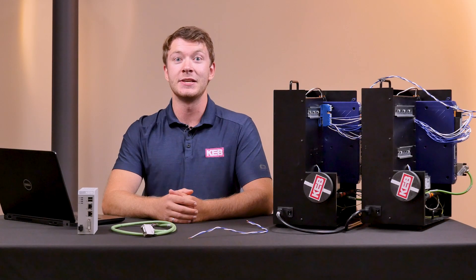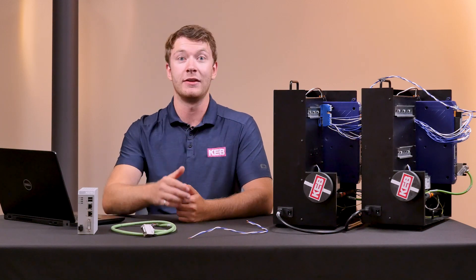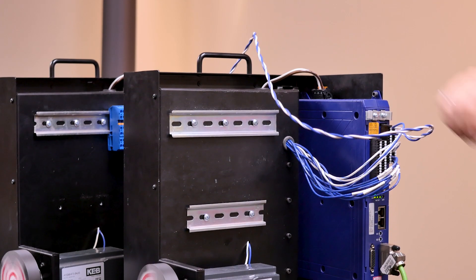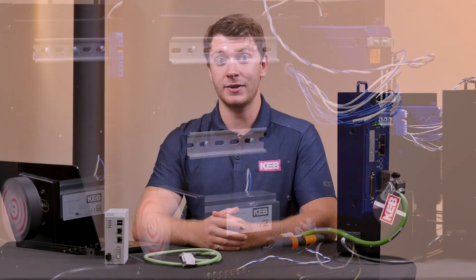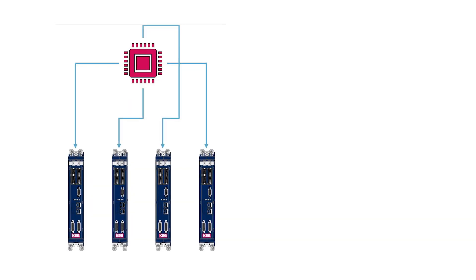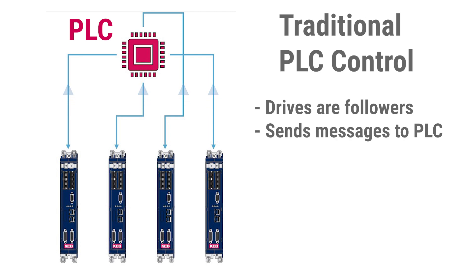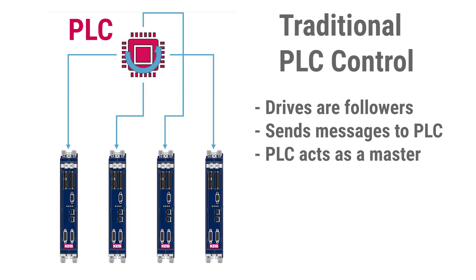CAN cross-communication is a KEB exclusive feature that enables direct data transfer between two drives over just two wires. In traditional CANopen networks, a PLC or some kind of controller would be required to manage all the data traffic going across the drives. The drives would be followers or command receivers, sending messages up to a PLC where those messages would be processed, and the PLC would act as a master, sending commands back to the drives.